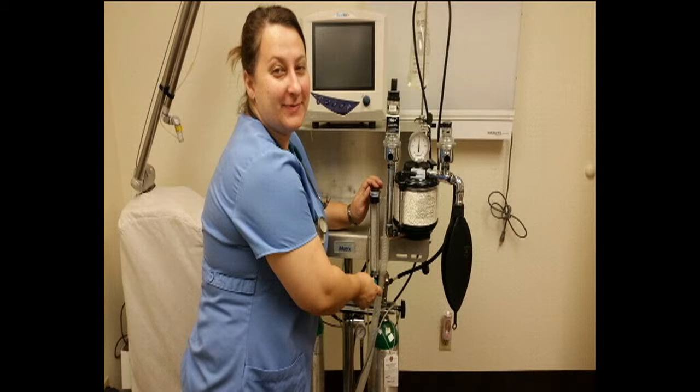The turner knob located on the bottom of the flow meter is used by anesthetists, and it controls the flow rate of oxygen. It turns on by turning the knob counterclockwise. The scale is read in liters per minute by looking at the ball indicator that rises with the gas flow. The ball is placed halfway on the line to the desired measurement on the meter. That means we read the ball right in the center.